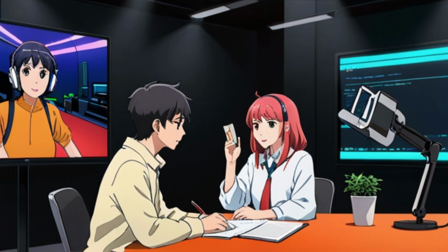I understand there are also refrigerant mixtures. How do we work with those safely and efficiently? It's important to distinguish between pure refrigerants and mixtures, which can be azeotropic or non-azeotropic. Azeotropic mixtures, starting with 5, like R500 or R502, behave like pure refrigerants and can be charged in any state. Non-azeotropic mixtures, starting with 4, like R404A, R407C, or R410A, however, should always be charged in liquid form, as their components behave differently in a gaseous state.